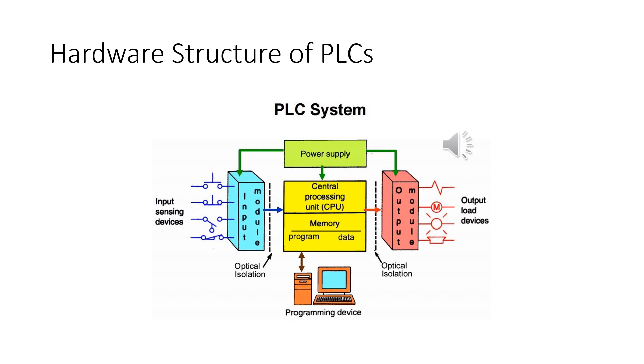In this slide, we have a drawing representing the PLC system, which consists of a power supply and the CPU — the central processing unit of the PLC. It has memory space divided into program memory and work or data memory, in addition to the input module and the output module. The input module is where input devices are connected, and the output module is where the output devices being controlled are connected. Finally, we have the programming device, which is normally a PC with a special application providing the programming environment of the PLC.